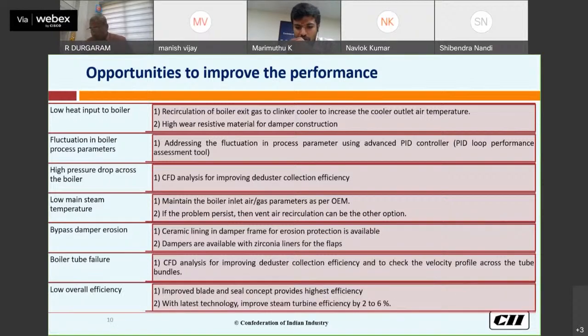So for low overall efficiency, turbine aging may be the reason, or I may be getting low input steam temperature. In this case, nowadays turbines are coming up with the latest technology. So improving blade and seal concepts provide the highest efficiency. With the latest technology, the old turbines can be retrofitted, and we can improve that efficiency by 2 to 6%.